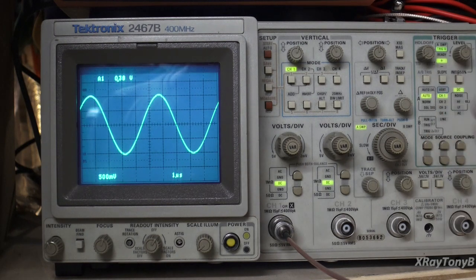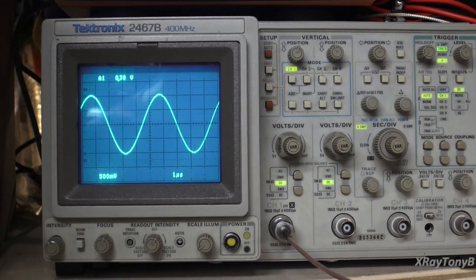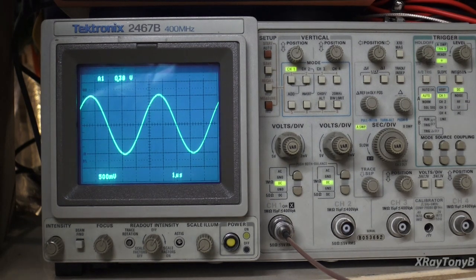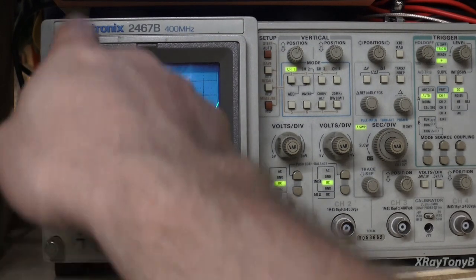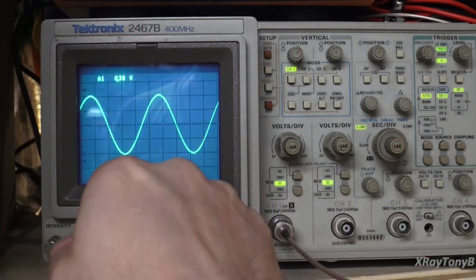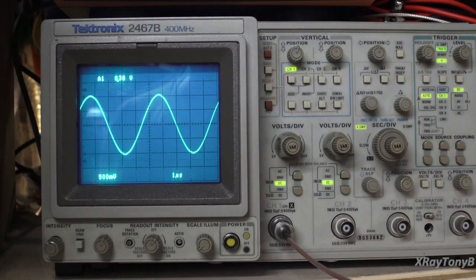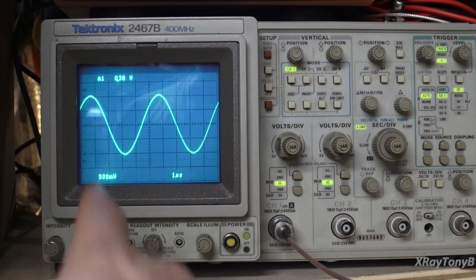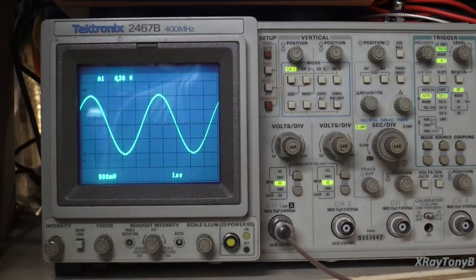Now, the reason we have plus and minus is because sometimes you're looking at something that is only going to go in one pulse. And it may only pulse up or down. If it's pulsing positive and you have it set to looking for a negative going wave or negative going trigger, it's not going to trigger until the waveform is done and comes down. And conversely, if you have a negative going signal that goes positive and it's just one pulse, it won't trigger.